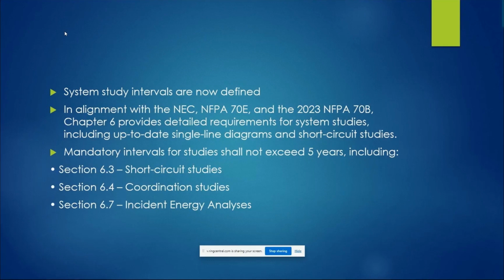But a lot of us fit into the normal duty or standard duty, which is, again, every year do an infrared scan. And then, of course, a housekeeping inspection every 5 years, things like that. Other things I should mention, this third bullet point here: mandatory intervals of study shall not exceed 5 years. Again, 60 months is the maximum interval for which you can go without any piece of equipment not being addressed in your program.